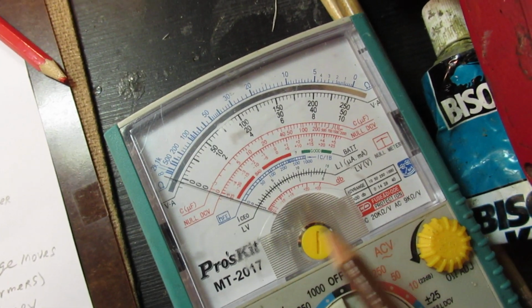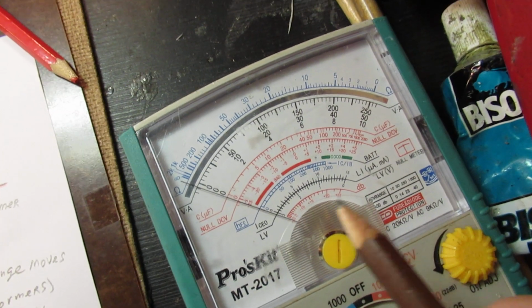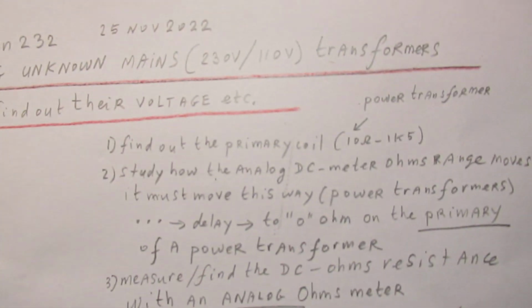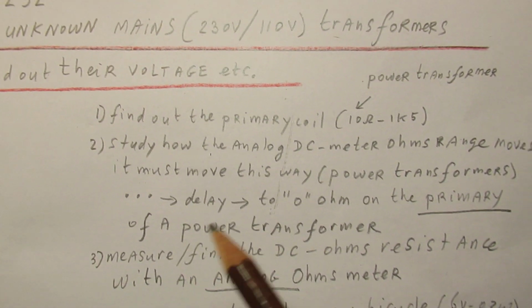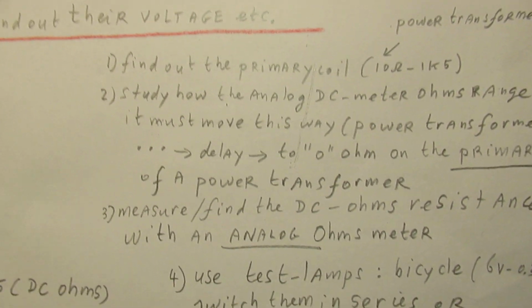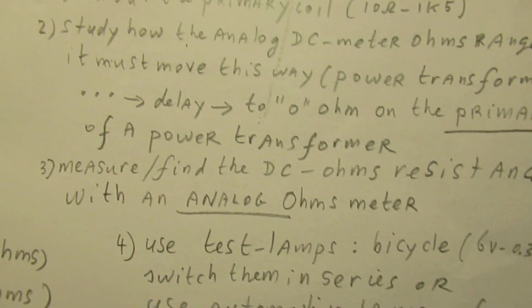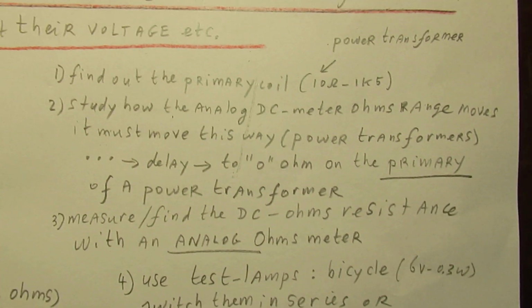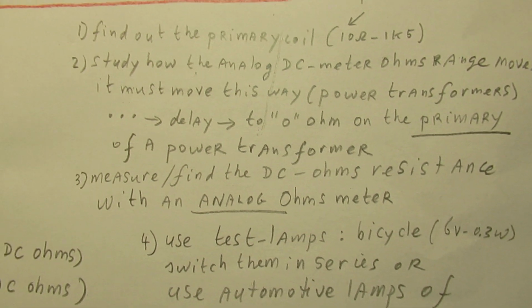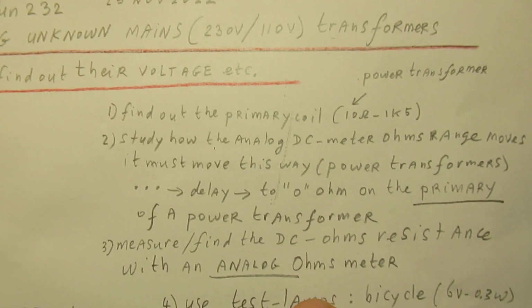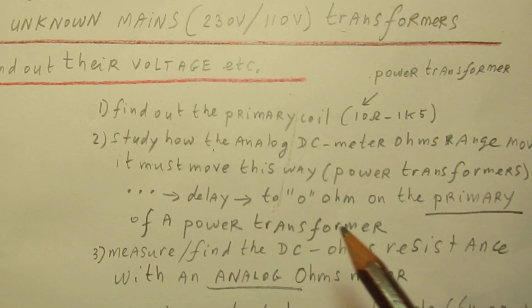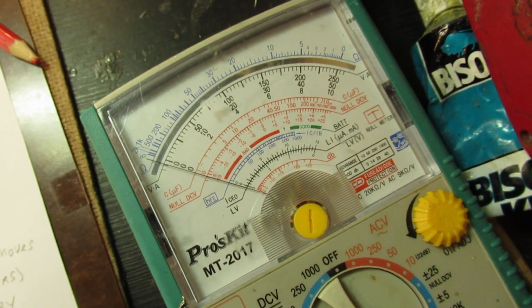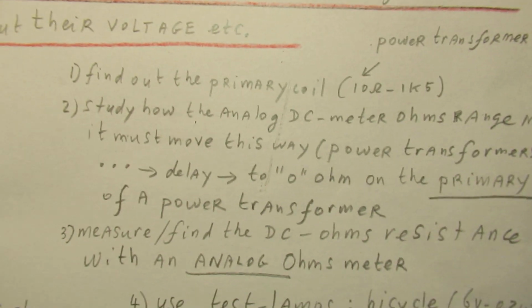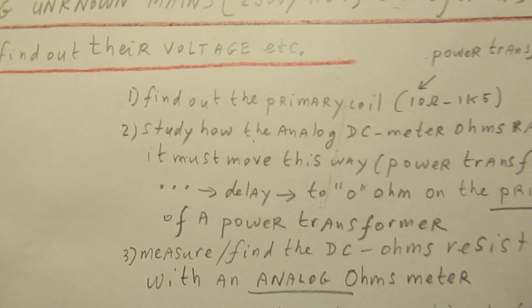But of course that same effect will also happen when you do such a measurement on the secondary coil. Still, it is a good indication that you are measuring a primary coil. So find the DC ohms resistances of the primary and secondary with an analog ohms meter, not a digital one - digital doesn't give the right information, especially about this back electromagnetic force effect that's generated when you connect a DC source to a coil.